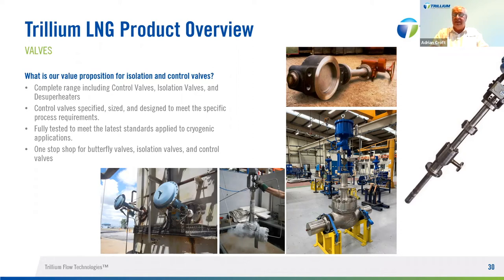So the valves are specifically designed so that all the trim within the valve is completely retractable and serviceable once you take the actuator and the top of the valve off. So the valve stem, the seat, etc., can be fully serviced once the top is removed from the valve. So very important for cold box applications.